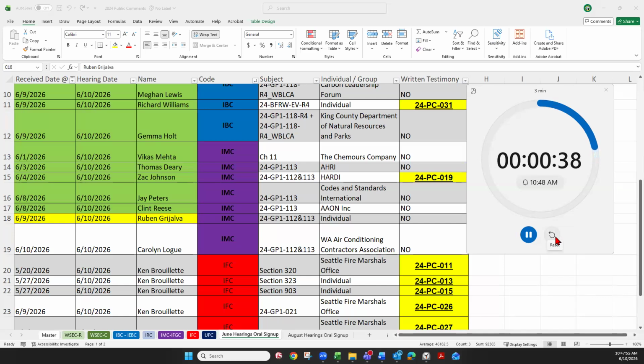UL 60335-2-40 references ASHRAE 15 for instances in which installation concerns need to be addressed. IEC references ISO 5149, which is significantly less prescriptive and allows for individual risk assessments to be performed for given installations. This is a fundamentally different approach to installation safety that is incompatible with the framework used in North America. In addition, the qualified products list is not a substitute for NRTL certification. NRTLs are required by OSHA to undergo rigorous evaluation to ensure their competency in evaluating products and performing testing in a repeatable and accurate manner. AAON respectfully urges the council to reject Proposal 24-GP1-113.